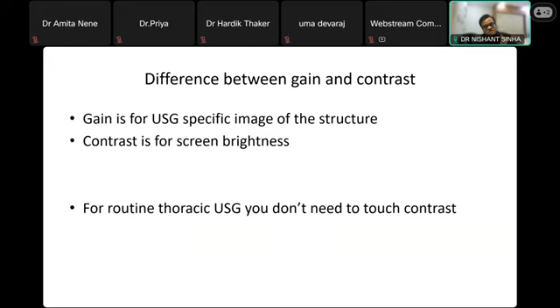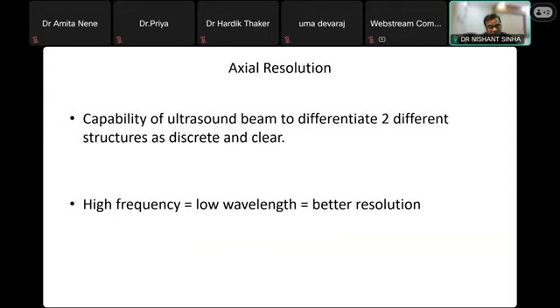Again, there's a very important topic called resolution. Resolution is when you can identify two structures as different. I told you already, if you're using a high frequency, you can have good resolution, but you'll have low wavelength, and it can't go deep. So this example shows the same thing, that as the waves go in and come back, they summate to give us the picture that we see as black and white in the lower part.